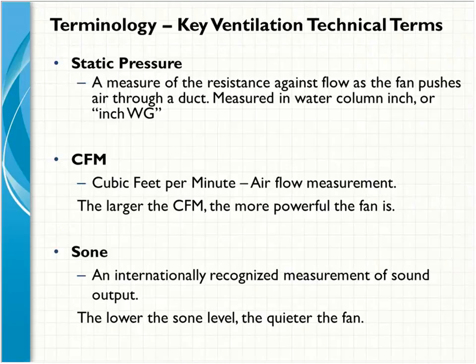Probably the one that people may not be quite as familiar with is static pressure, and that's a measure of the resistance to airflow that a fan might meet with ductwork and the termination. So the higher the static pressure, generally speaking, the more resistance there is, and the lower the CFM would be for that product. It has a negative impact. The higher the static pressure, the more it will impact the performance of the equipment. And that's why we're going to talk near the end of the presentation about proper installation, because as I said earlier, you can buy the best equipment in the world, but if it's installed improperly, or you add too much ductwork or a poor termination, the equipment's not going to perform the way it's designed. So that's the important one there.